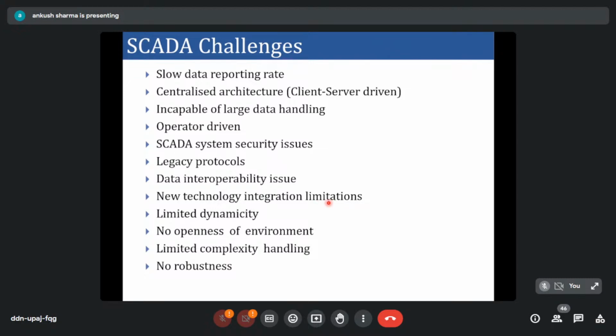If you want to integrate PMU with the SCADA system, you face a lot of challenges because the data reporting rate of PMU is very fast when you compare with the legacy RTU system.